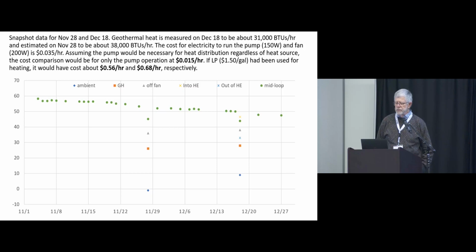So the cost for running the pump was 150 watts. We're paying about a dime per kilowatt hour for electricity, so it's about a penny and a half an hour to run that pump. If you were to get 31,000 or 38,000 BTUs out of a gallon of LP at $1.50 a gallon, it would cost you about 56 cents an hour or 68 cents an hour, respectively.